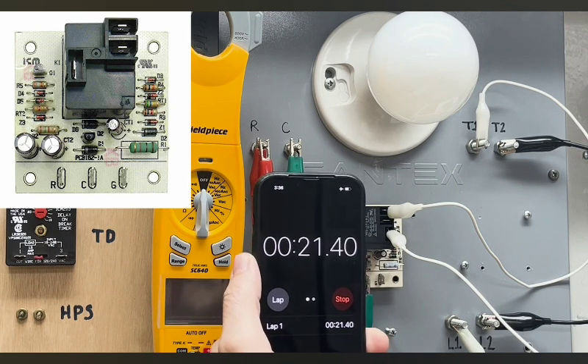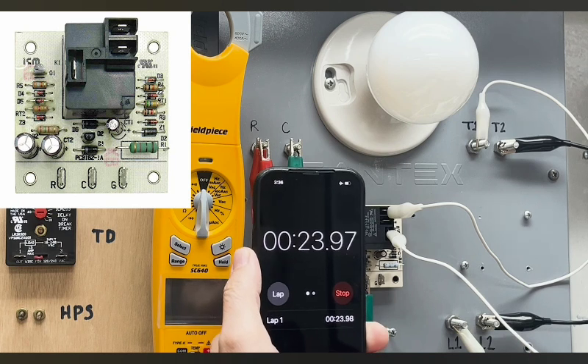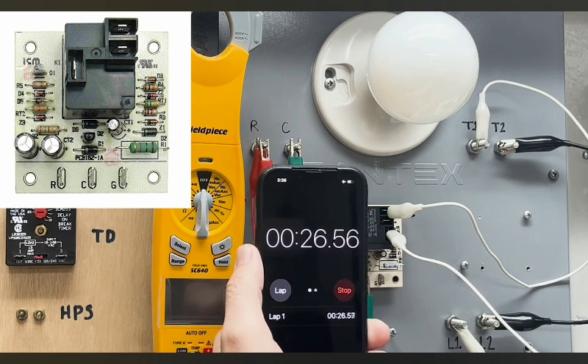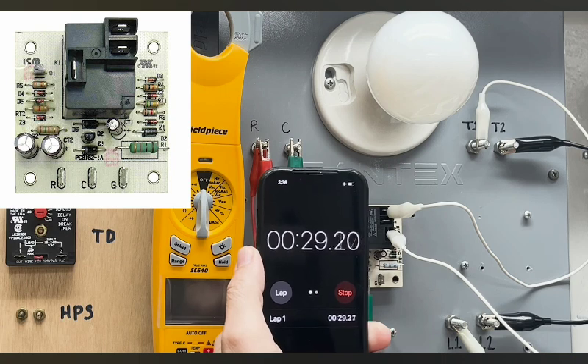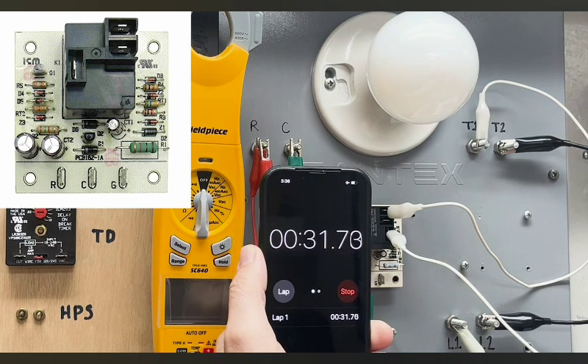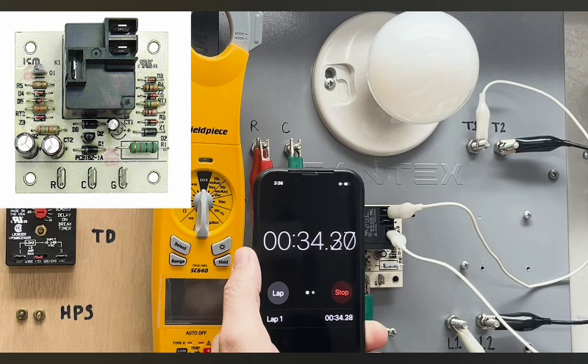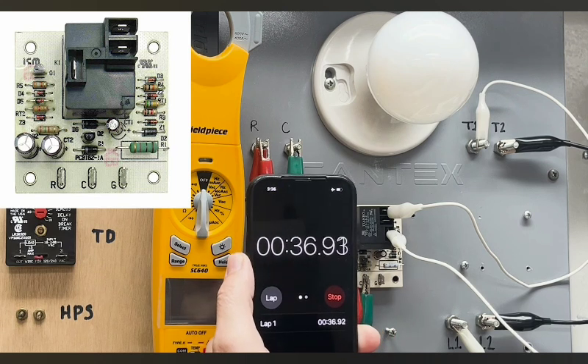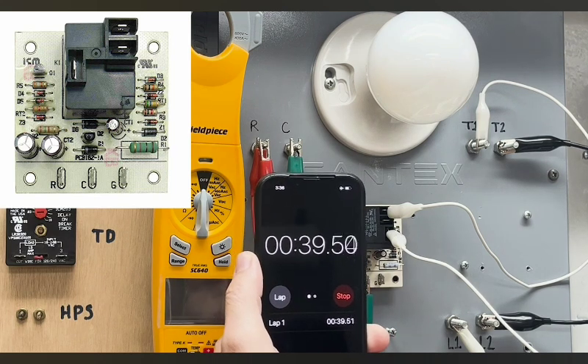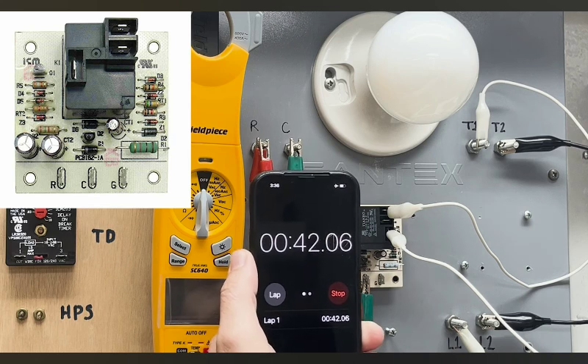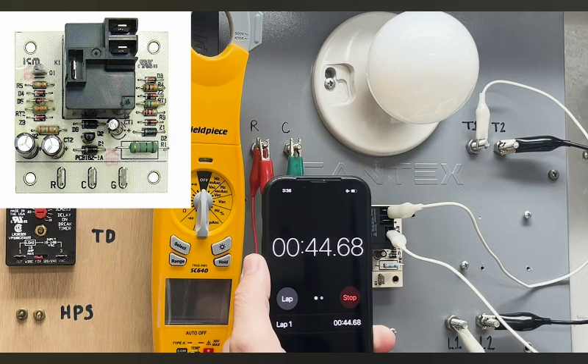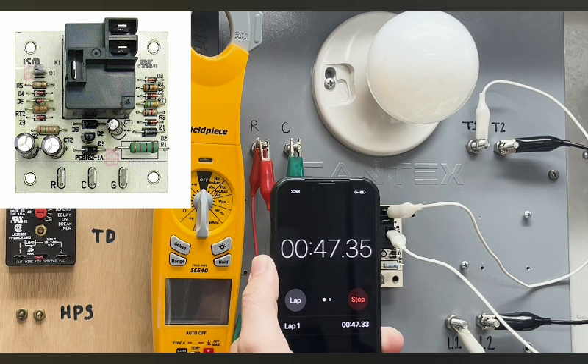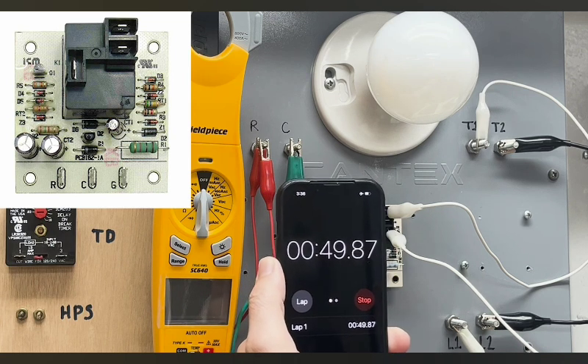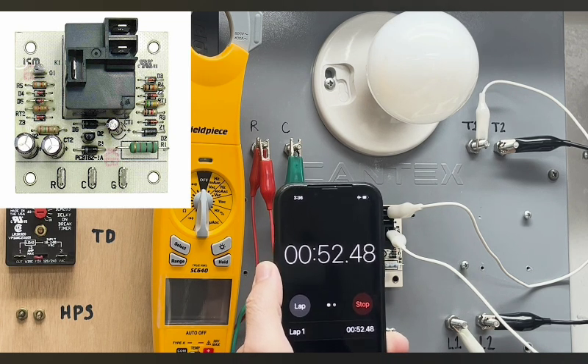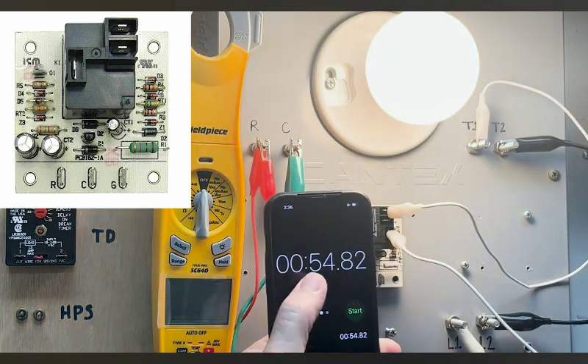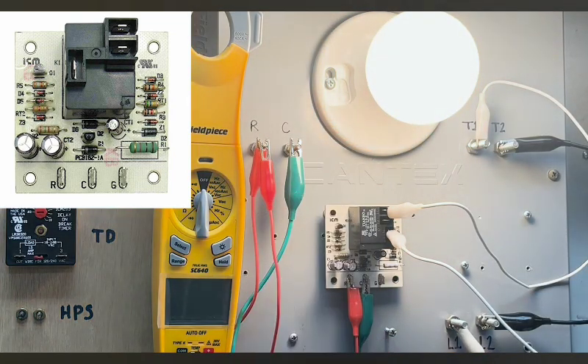And so that's good if I wanted to use this relay to wire two different loads up to it, where there's 50 seconds on one load and then 50 seconds on the other load, whether it's on or off. So this is giving me an on delay and an off delay in between normally open and normally closed. Any minute now it should energize. Right around 50, 52 seconds. There we go. And so we had about 52 seconds there, and now our normally closed is energized.